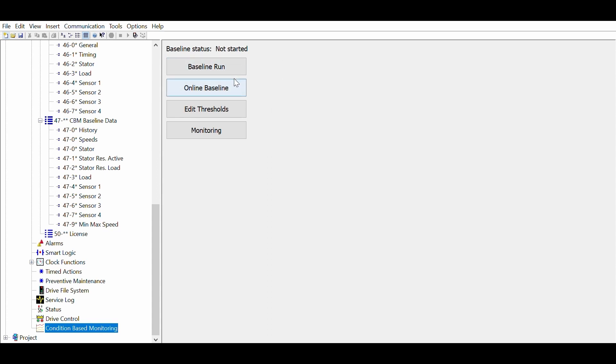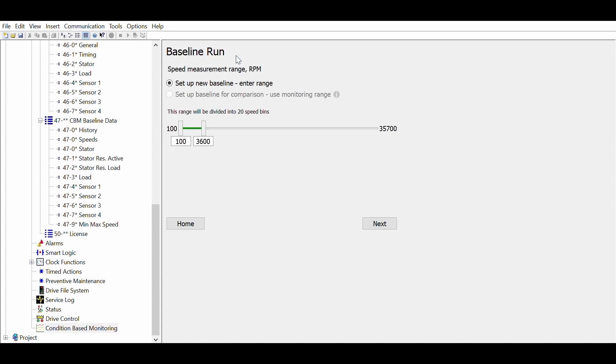There are two ways to establish the baseline: either through a baseline run, where the drive sweeps through a defined speed range, or an online baseline where the drive collects data during normal operation. For demonstration purposes, let's use the baseline run.